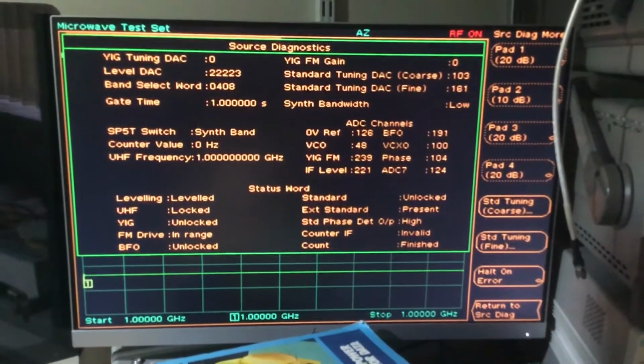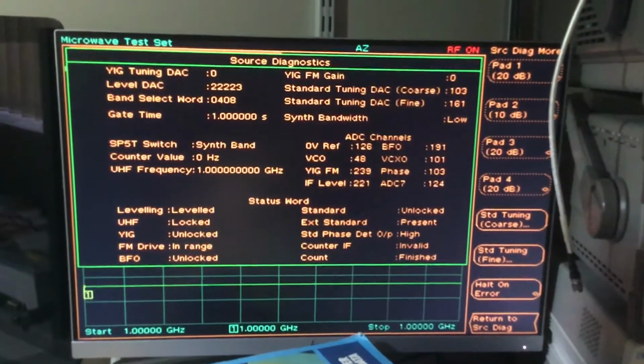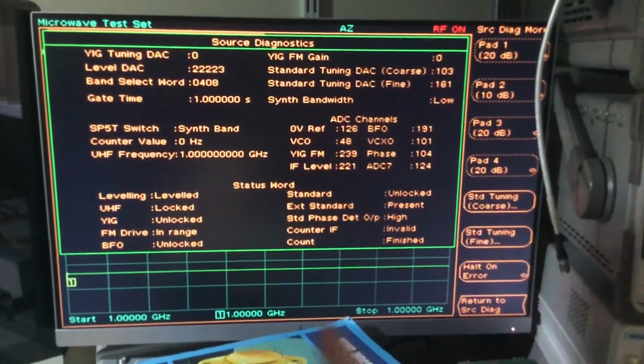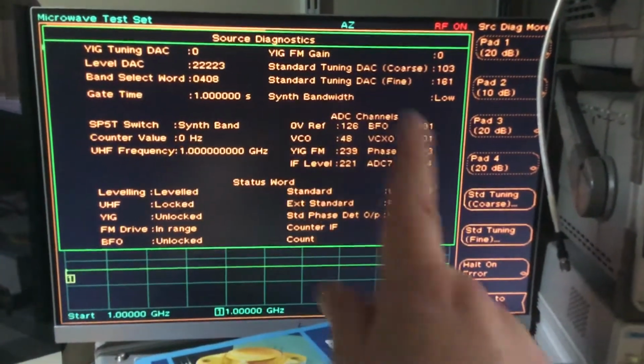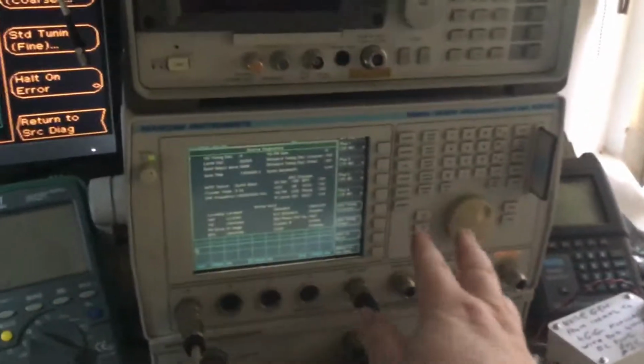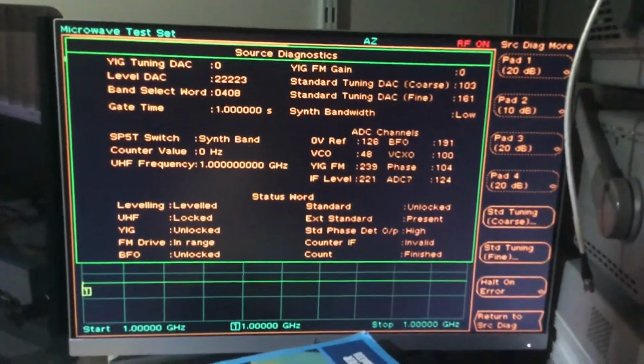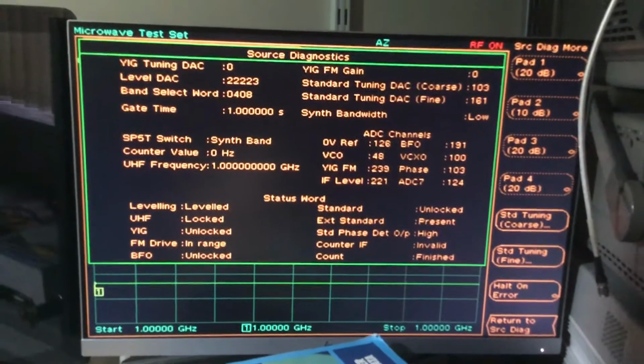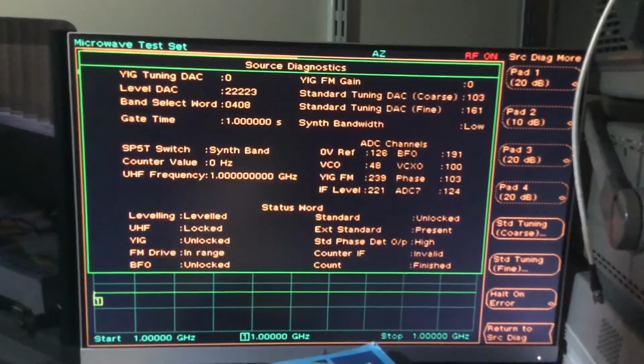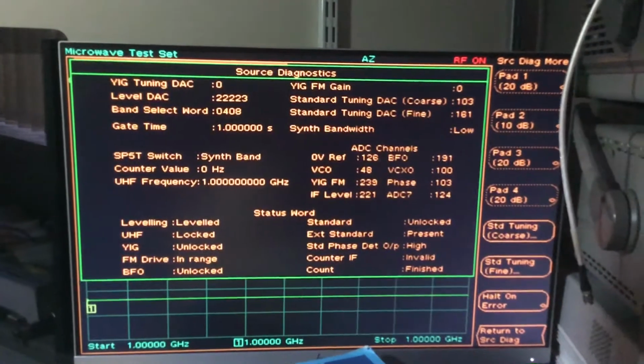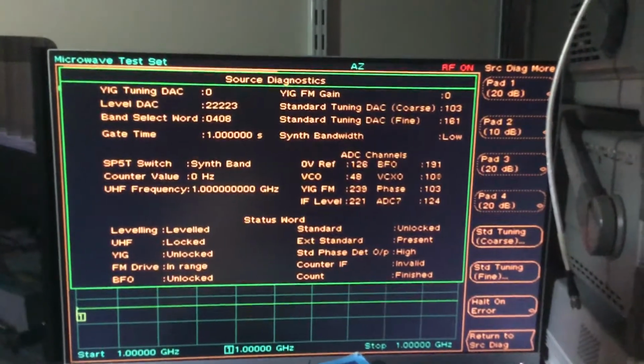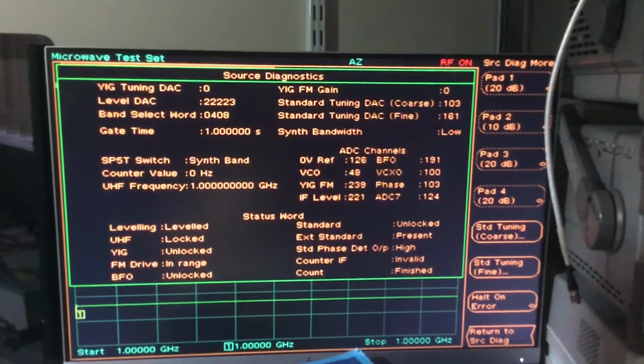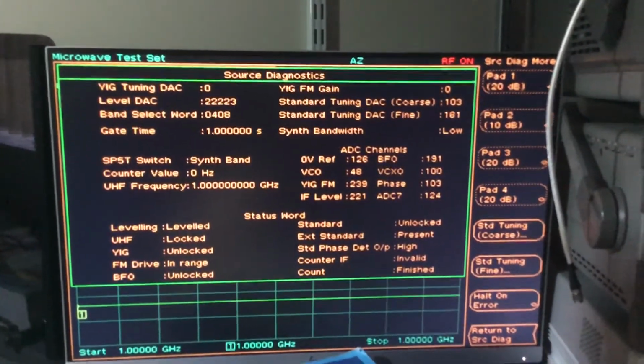And then what happens is that it's like a phase lock loop. It keeps itself locked in a loop, and whenever that level's there, it'll maintain a constant lock loop of RF output. The moment we change the level by altering the variable control here or manually inputting an RF level at a specific RF frequency, it will then recall its memory for that level and that frequency, which was from the calibrations menu, and then it will apply that and adjust the RF attenuator respectively so that it gives the correct RF output for that frequency.